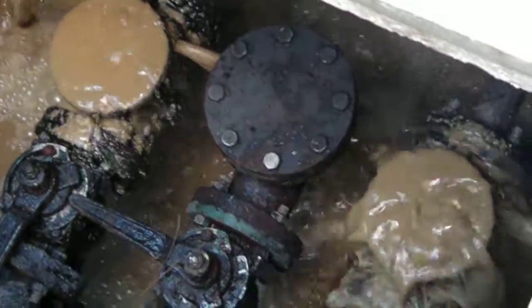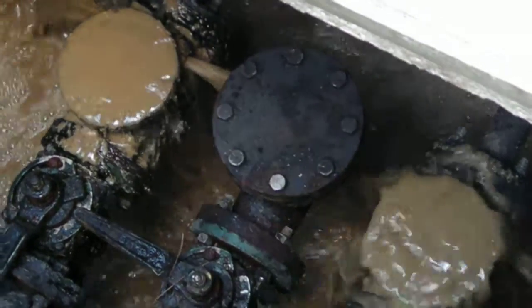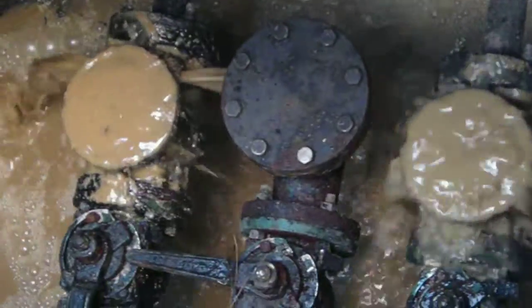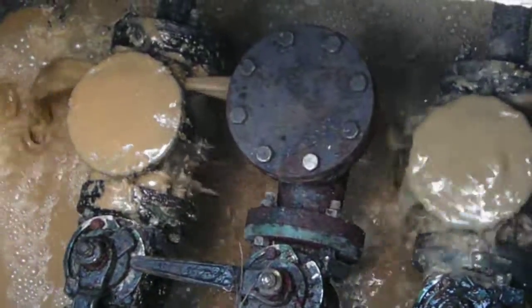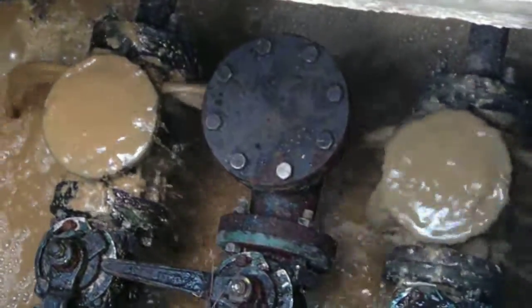As you can see, the pipes are just full of grease. We have the cheap check valve covers off right now, cleaned out the check valves, and these pipes that are coming out of the basin are nothing but grease.